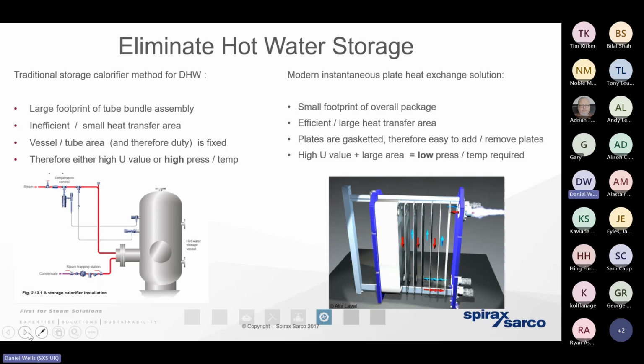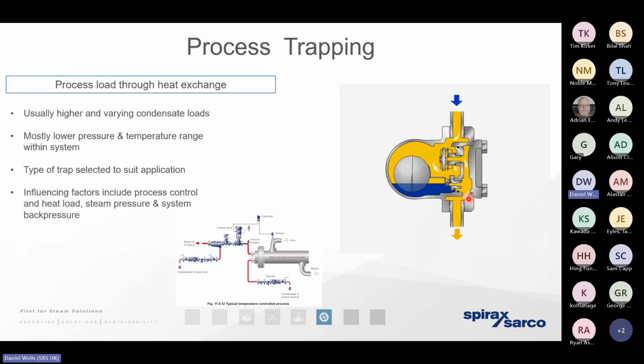We've minimized the risk of that energy loss through the hot water radiating its energy whilst it's held in the plant room. And the other reason is, if we're using a plate heat exchanger to generate hot water, it means that we've got a much bigger heat transfer surface area, as we can see on the image towards the right hand side of the screen, which in turn means we can condense the steam at a lower pressure and lower temperature, which, as we've already mentioned, means the steam's got far, far more energy in it, and therefore the boiler doesn't have to work as hard.